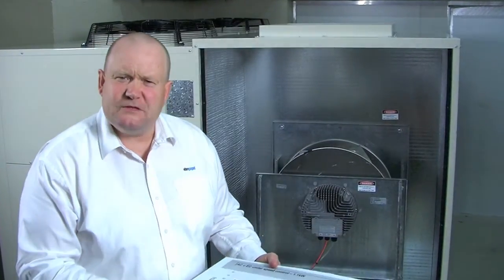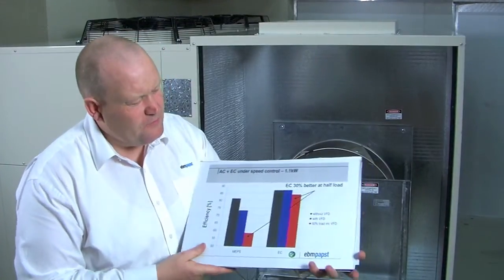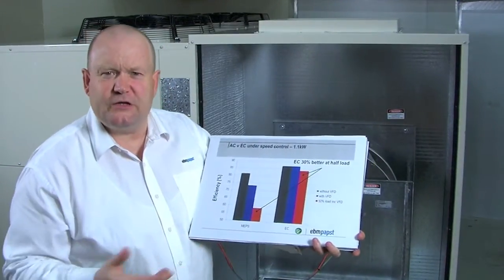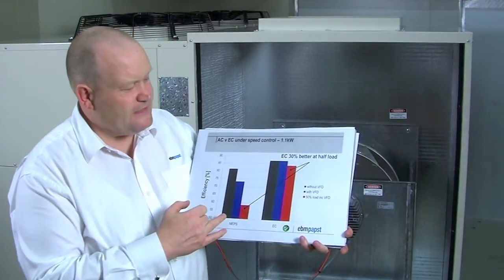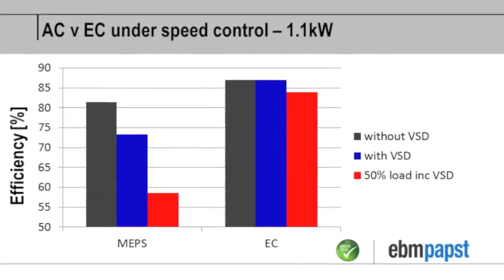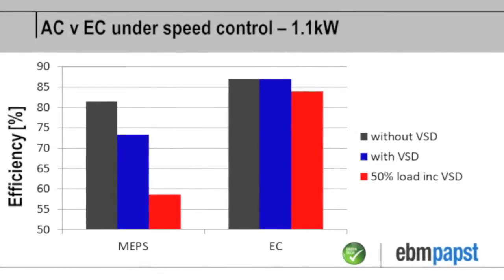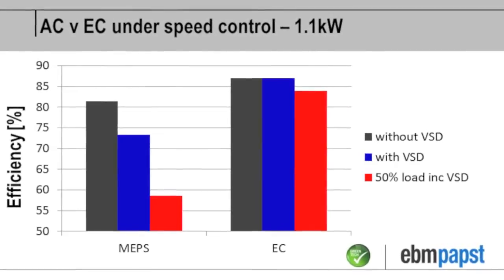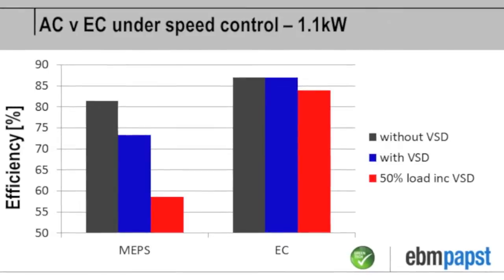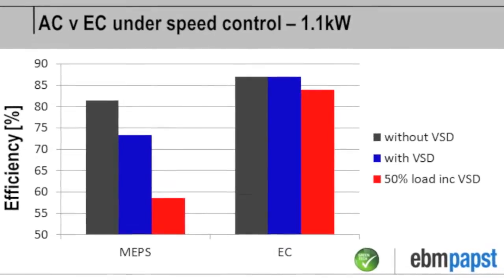So what happens when you speed control it? Well here again I've done a comparison of the products under speed control. Here you can see in the black the motor efficiency itself. In the blue what happens to the product if I add a VSD? So the blue with respect to the MEPS product drops because there's losses inside the VSD.